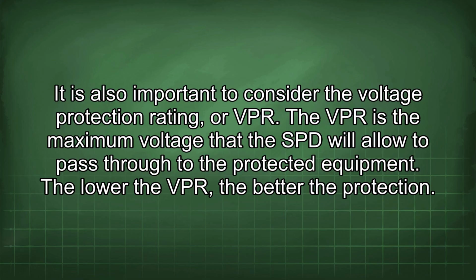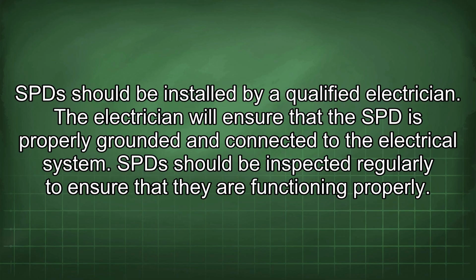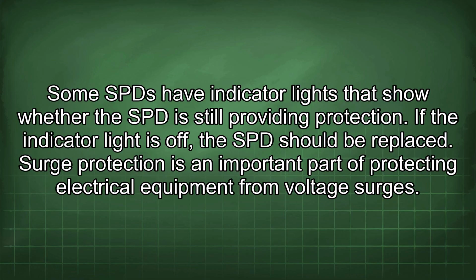The lower the VPR, the better the protection. SPD should be installed by a qualified electrician. The electrician will ensure that the SPD is properly grounded and connected to the electrical system. SPD should be inspected regularly to ensure that they are functioning properly. Some SPD have indicator lights that show whether the SPD is still providing protection. If the indicator light is off, the SPD should be replaced.